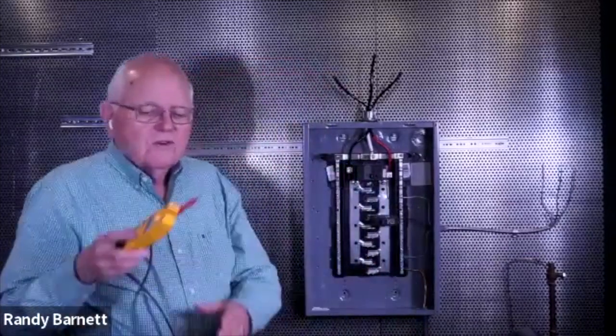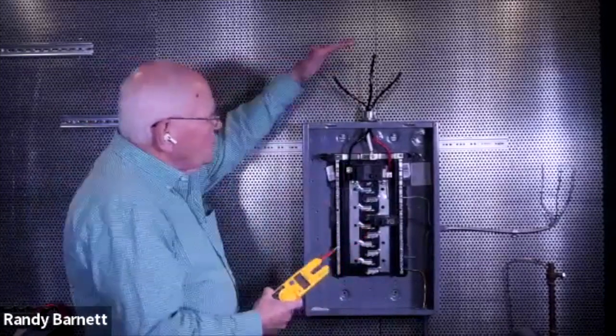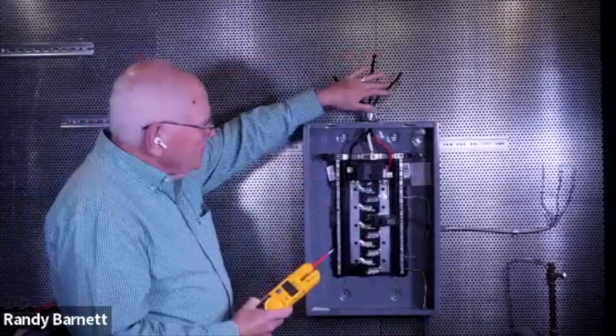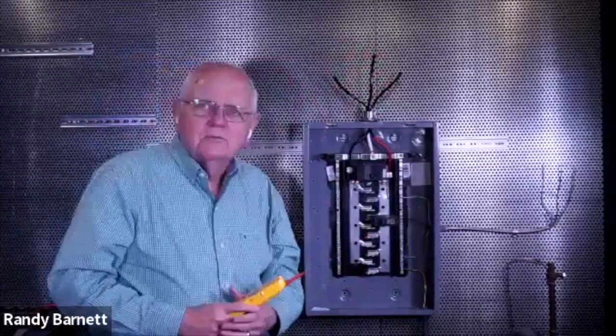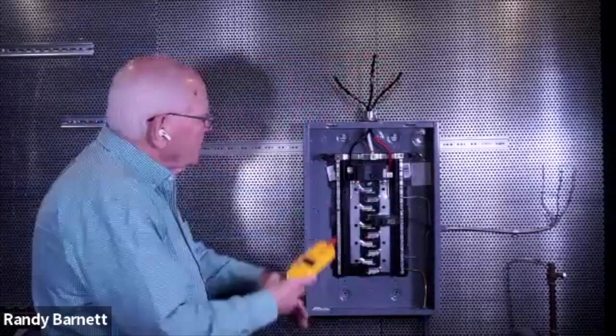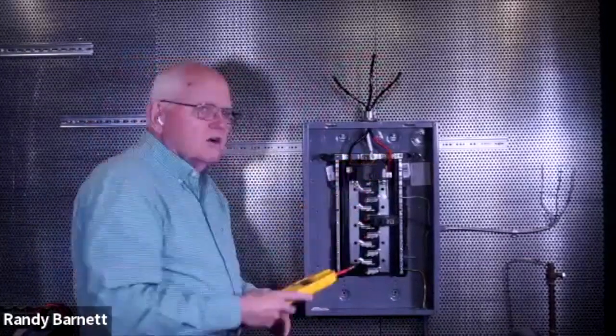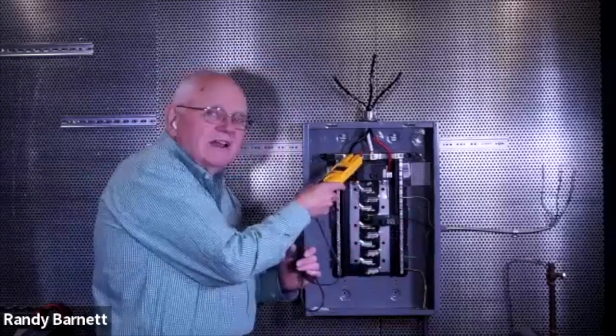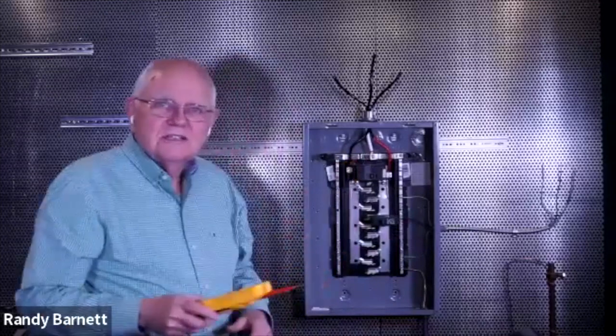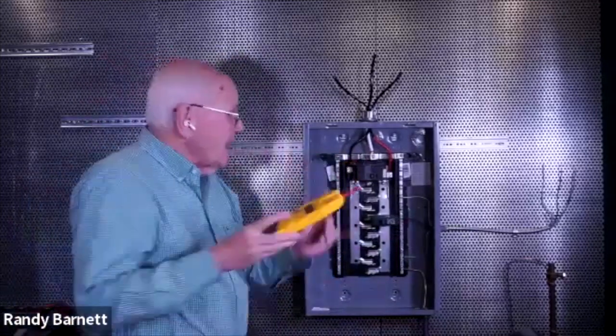So what are the right terms? Well, first of all, we have power that comes in from our service. These would be our service entrance conductors. That means it comes from the utility, doesn't it? And I've got three conductors here. I've got the black and the red, which are not hot wires. Those are our ungrounded conductors because they're not connected to ground. I do have one wire coming in that is white right here in the middle, and that is a grounded conductor.